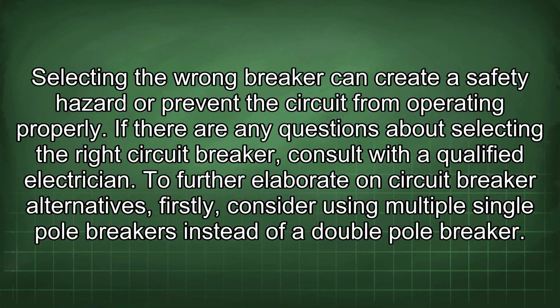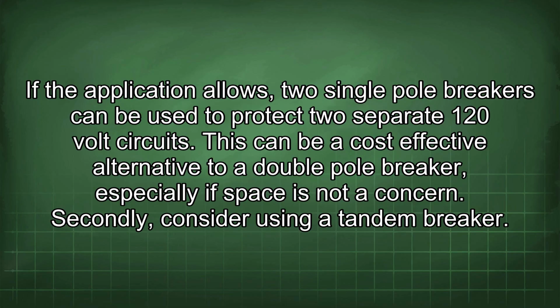To further elaborate on circuit breaker alternatives, firstly consider using multiple single-pole breakers instead of a double-pole breaker. If the application allows, 2 single-pole breakers can be used to protect 2 separate 120-volt circuits. This can be a cost-effective alternative to a double-pole breaker, especially if space is not a concern. Secondly, consider using a tandem breaker.